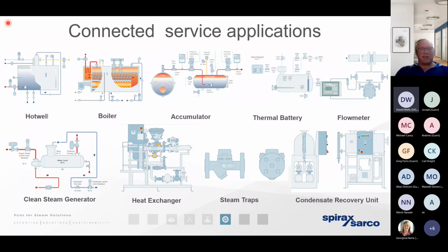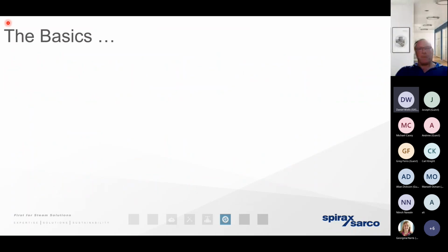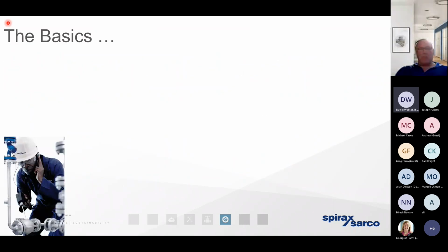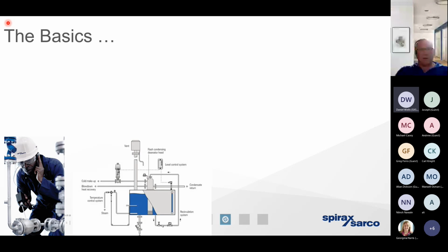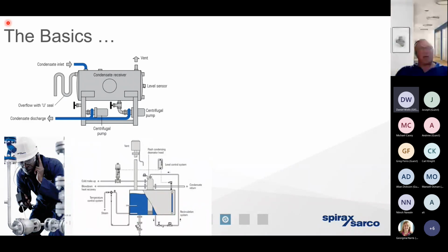So the good working practice, the basics we want to remember, it's things like making sure that our steam traps are adequately monitored so that they're not left failed in the open position. We want to keep the water in the hot well, in the feed tank, at the highest point possible. Remember, the steam tables tell us the hotter the water we're putting into the boiler, the less energy we need to consume to raise steam again. And one such way that we can keep the hot well at a nice high temperature is by recovering as much of that condensate as we possibly can.